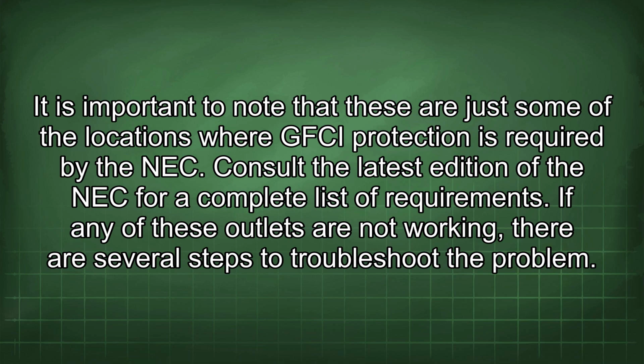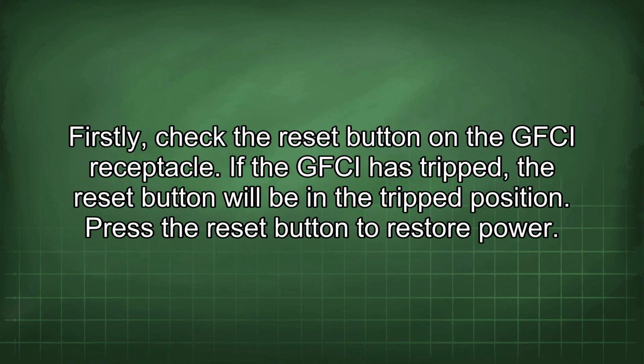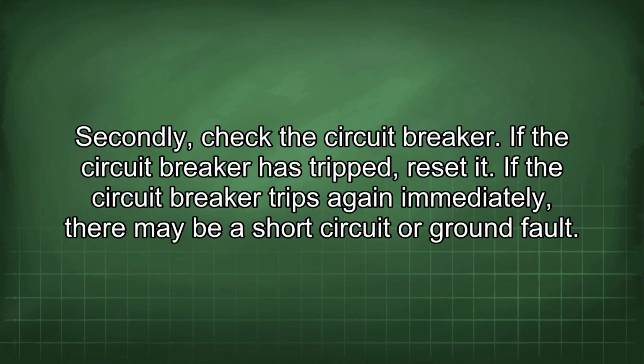If any of these outlets are not working, there are several steps to troubleshoot the problem. Firstly, check the reset button on the GFCI receptacle. If the GFCI has tripped, the reset button will be in the trip position. Press the reset button to restore power. Secondly, check the circuit breaker. If the circuit breaker has tripped, reset it. If the circuit breaker trips again immediately, there may be a short circuit or ground fault.